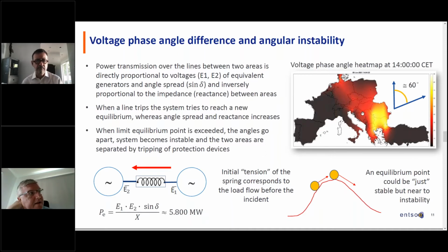And then when we lost the line from Subotica Novi Sad in Serbia, we passed the 90 degrees limit, and the two systems started to oscillate, one compared to the other. So they were not in synchronism anymore. So where we usually have the whole continental Europe system, the whole map completely synchronized, at exactly the same frequency, the south-east part of Europe started oscillating compared to the north-west part.